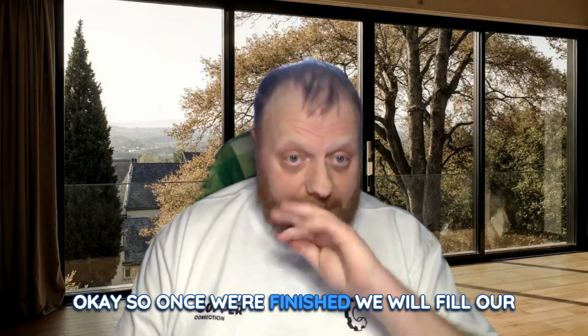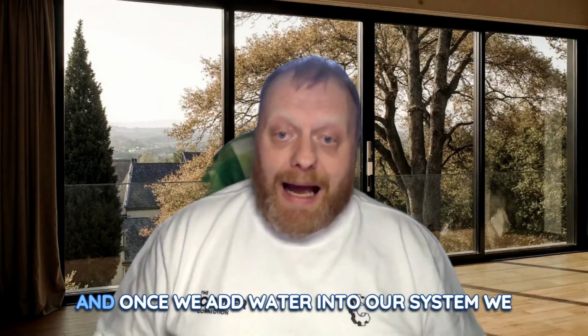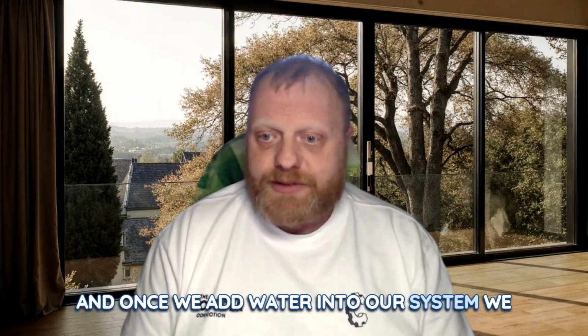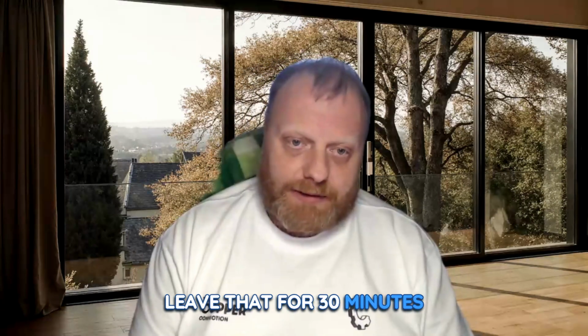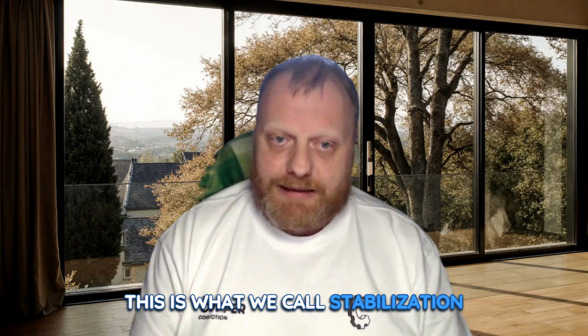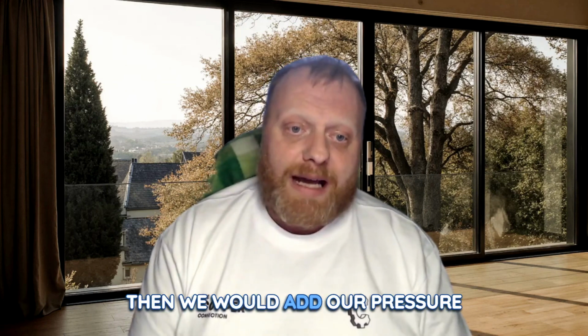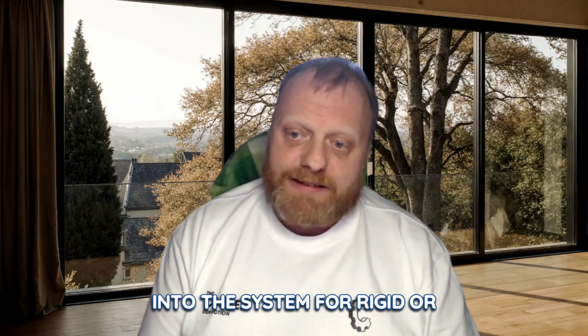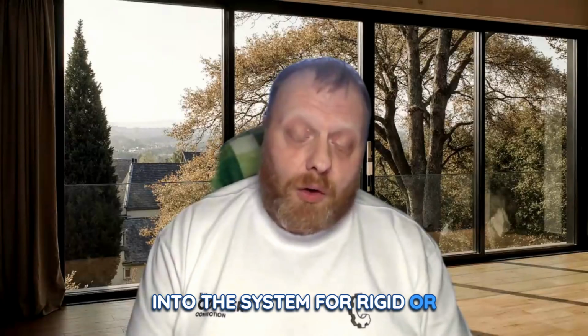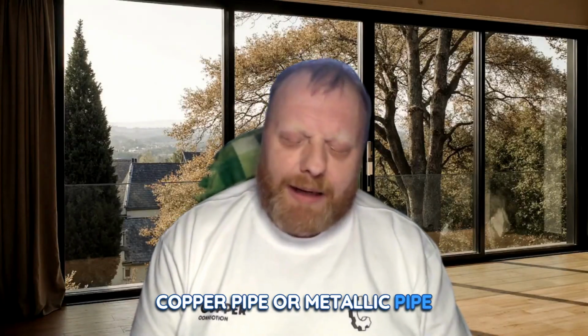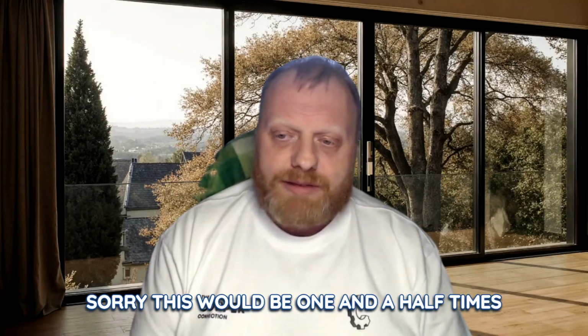Okay, so once we've finished, we will fill our system up, and once we add water into our system, we leave that for 30 minutes. This is what we call stabilisation. Then we would add our pressure into the system. For rigid or copper pipe, or metallic pipe, this would be 1.5 times working pressure.